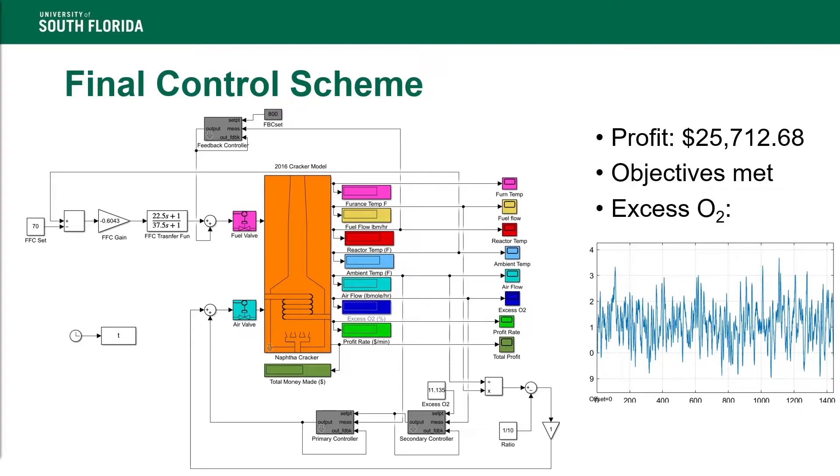After evaluating both alternatives, Alternative 1 showed better control of the excess O2. Alternative 1 was combined with a ratio control, where the ratio controller adjusted the position of the air valve based on the fuel flow to the air flow, which had a ratio of 1 over 10. The set point of the excess O2 had to be raised to 11.135%, which lowered the profit. The tradeoff here was between the profit and the excess O2, but to ensure safe operation of the plant, the loss in profit was seen as acceptable. The final profit was $25,712.68. The objectives were met as profit was maximized and safety was not compromised. While occasional dips below 10% remained, the excess O2 never dipped below 9%.